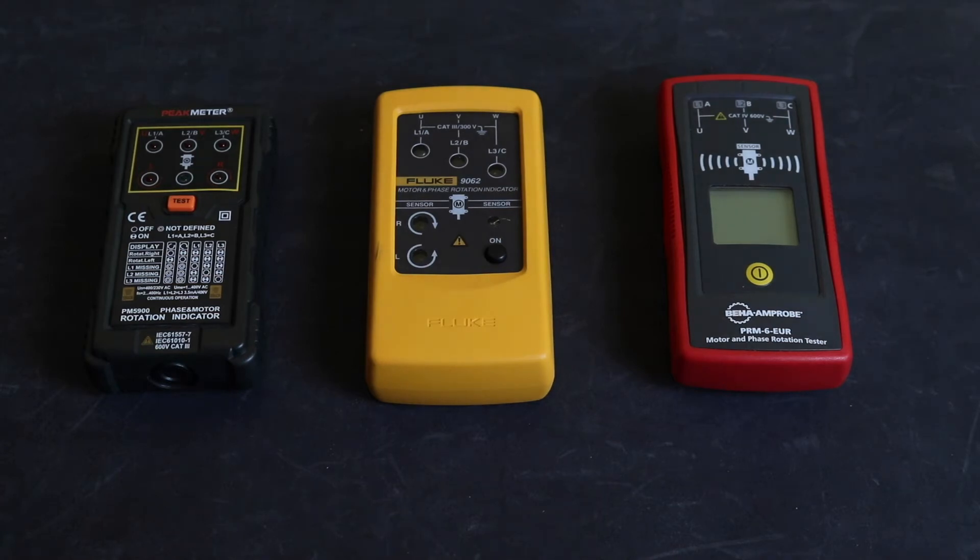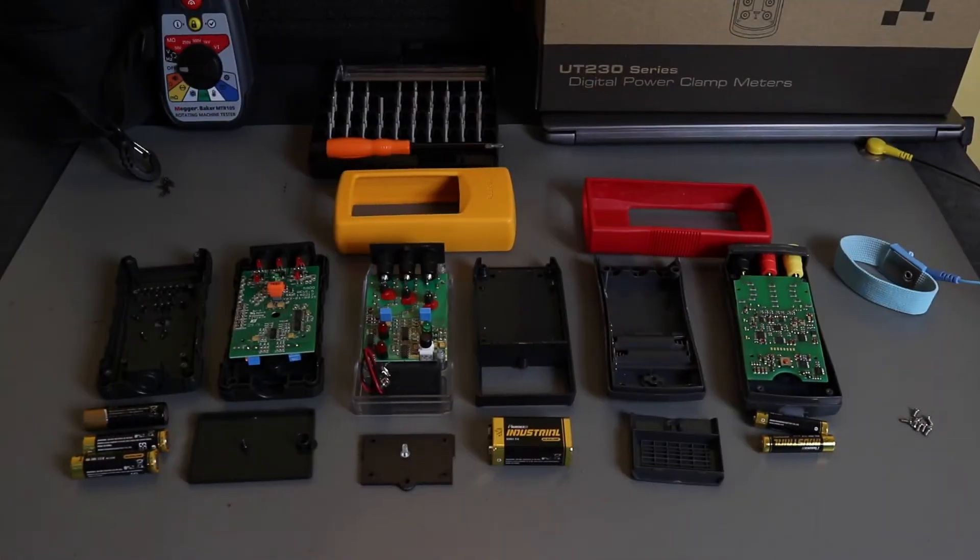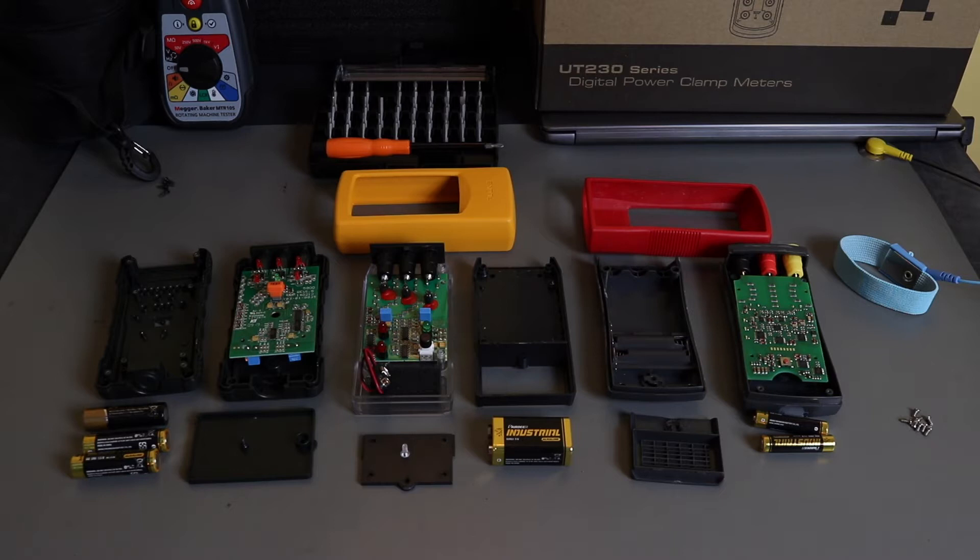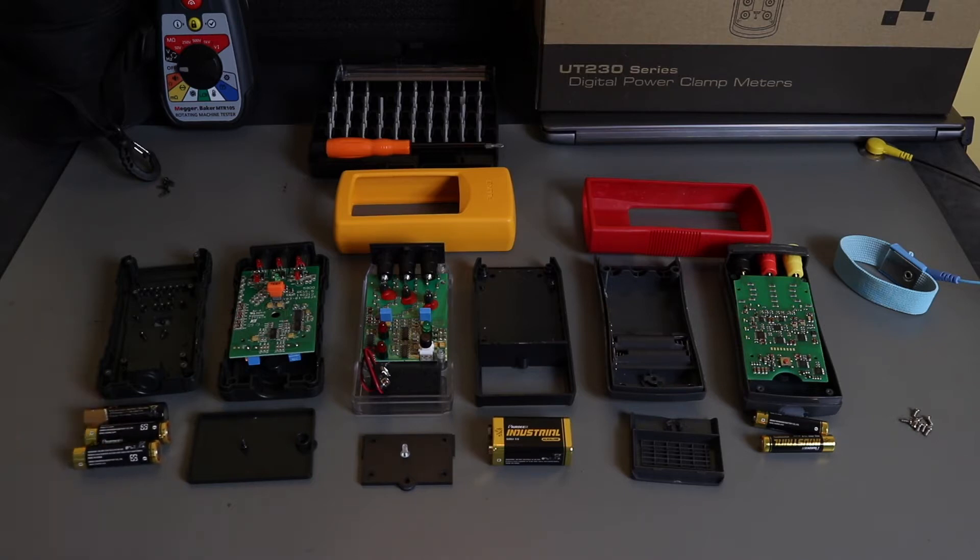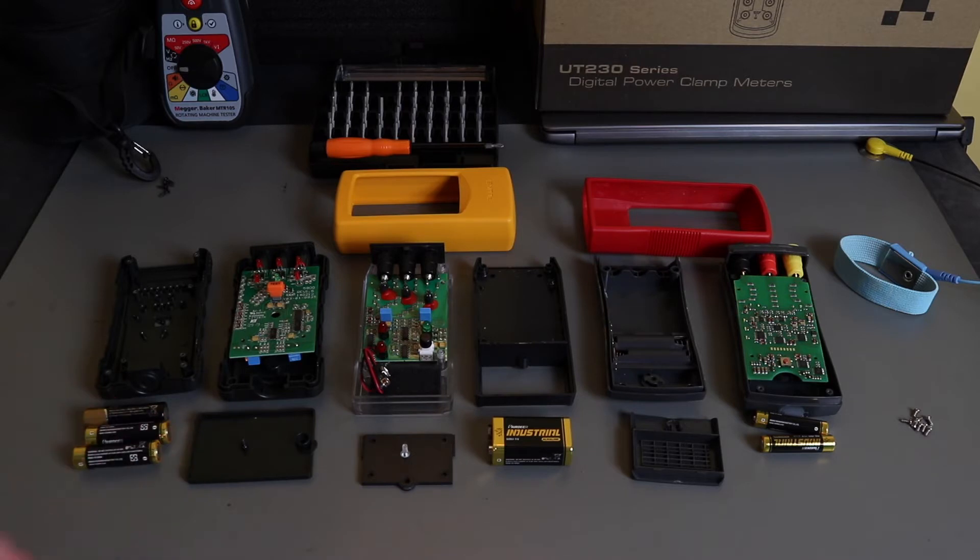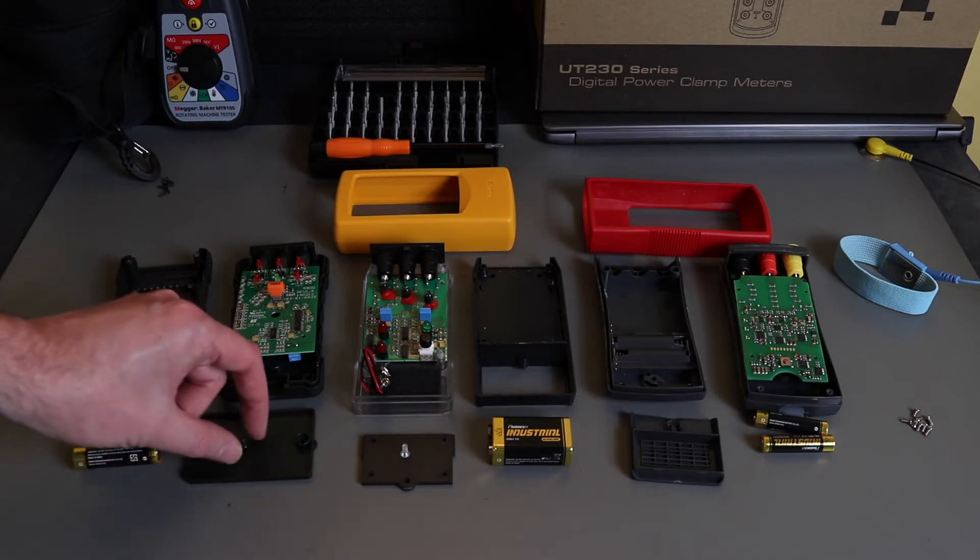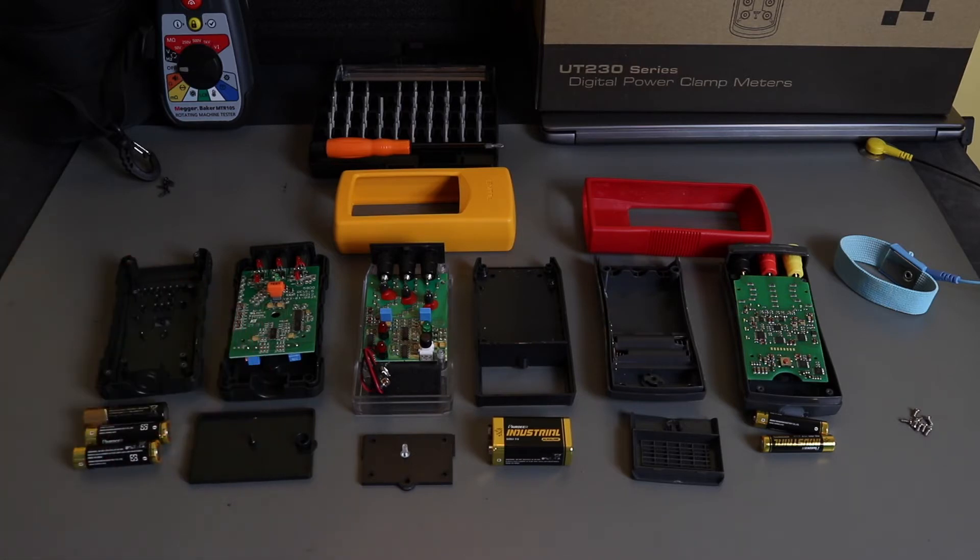We've got into all three phase rotation meters. I've got the Peak meter on the left here - completely solid plastic case all around, three batteries, separate battery compartment lid that comes away completely, and the retaining screw is not retained within the lid, so easy enough to lose.